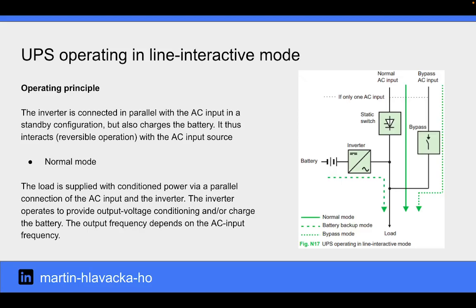A UPS operating in line interactive mode has the inverter connected in parallel with the AC input in a standby configuration, but it also charges the battery. It thus interacts with the AC input source. In normal mode, the load is supplied with conditioned power via a parallel connection of the AC input and the inverter. The inverter operates to provide output voltage conditioning and charge the battery. The output frequency depends on the AC input frequency.